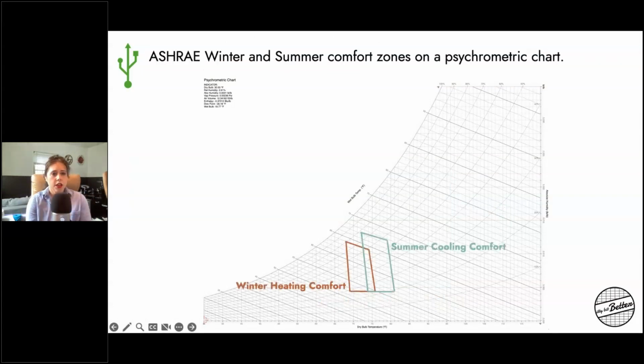Also, when we look at ASHRAE and occupied spaces, we're typically keeping our cooling within two ranges: summer cooling and winter heating. I know the numbers on the bottom are really small, so just to give you an idea, winter typically ranges between 68 and 74 degrees Fahrenheit, and summer ranges between 72 and 80 degrees Fahrenheit with a relative humidity between 30 and 60%.